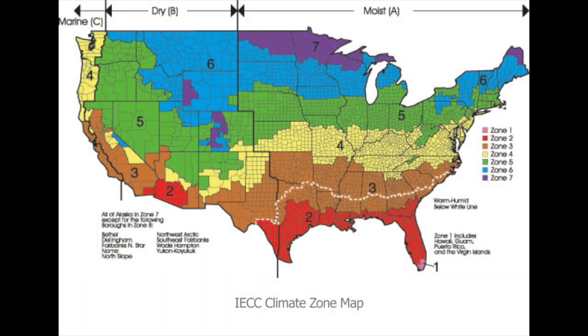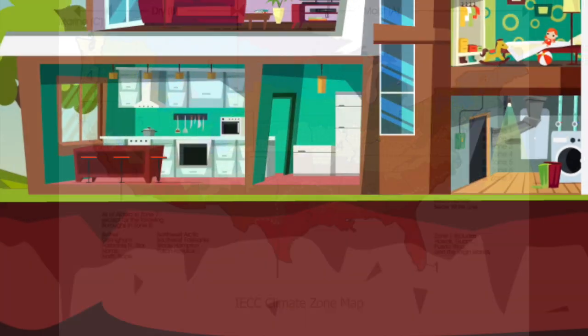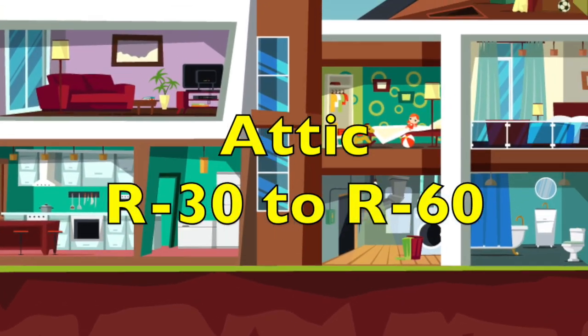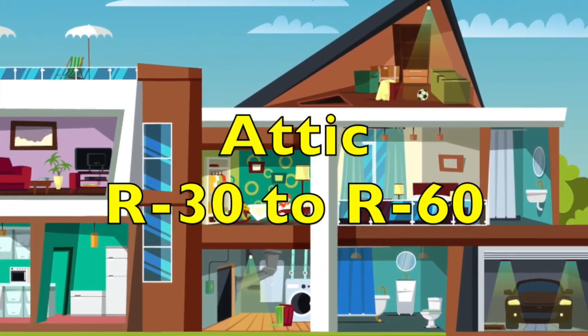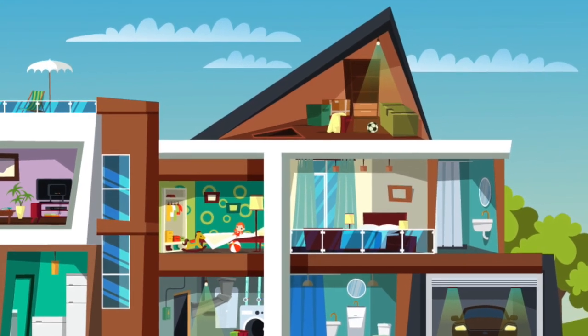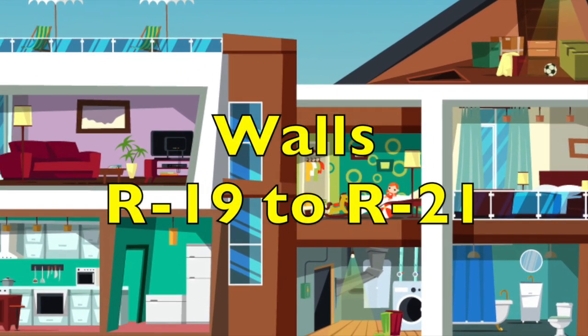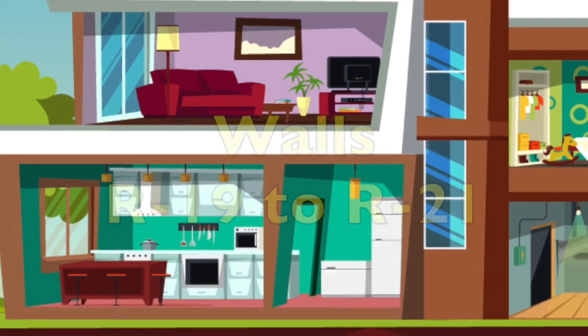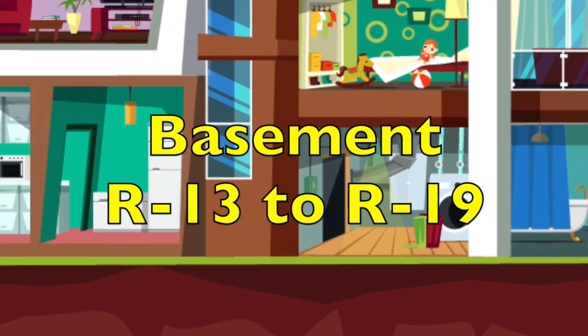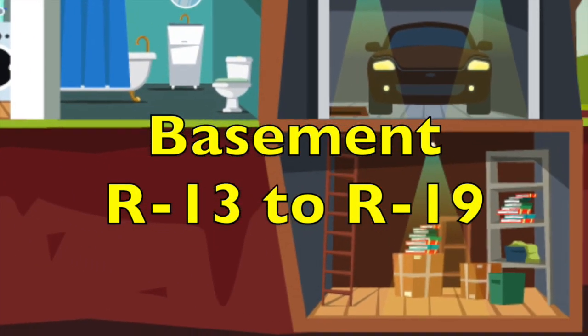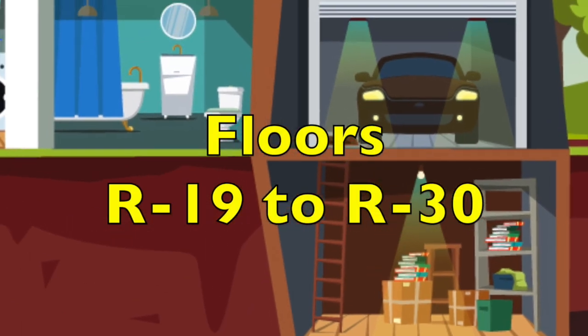Different climates require different R values. The higher R values in the range are for the colder climates with more heating days. For most climates, an attic is between R30 to R60. Walls should be at R19 to R21. Basement walls R13 to R19, and floors from R19 to R30.